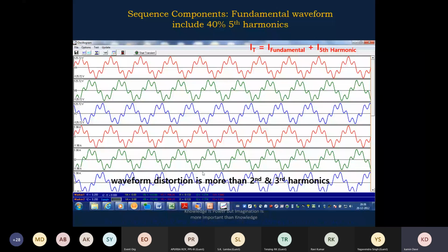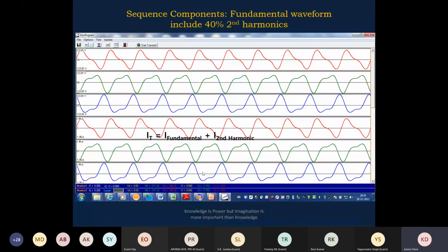the higher the order of the harmonic, the more it distorts the waveform. For example, say second harmonic 40% and 10th harmonic for example say 5%, the distortion will be high even though it is only 5% of 10th harmonic, but the distortion will be more in that case, total harmonic distortion. So second harmonic, third harmonic, fifth harmonic, you look at it here.